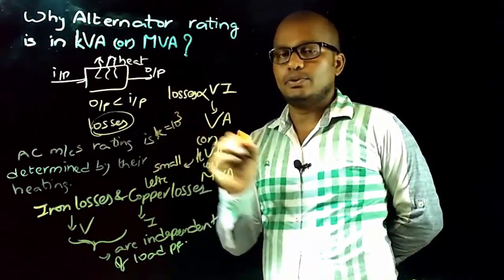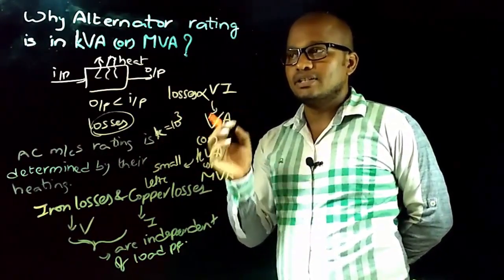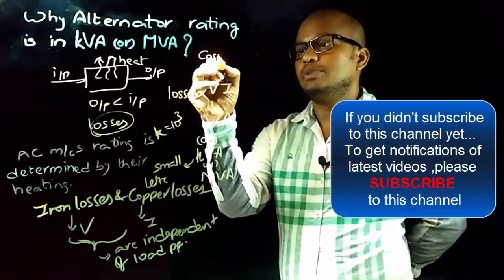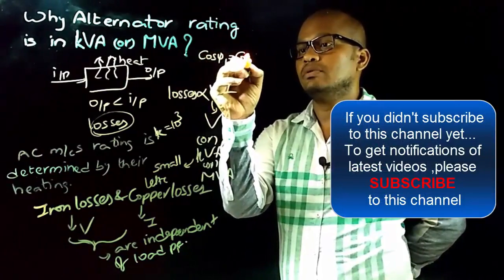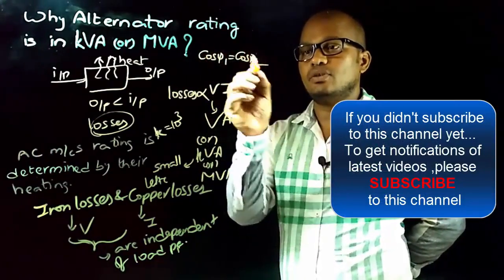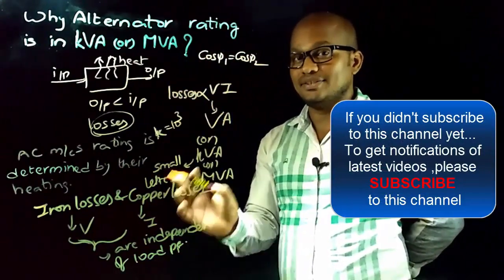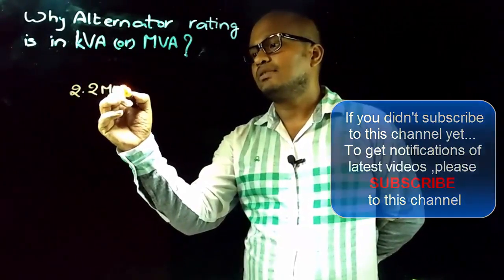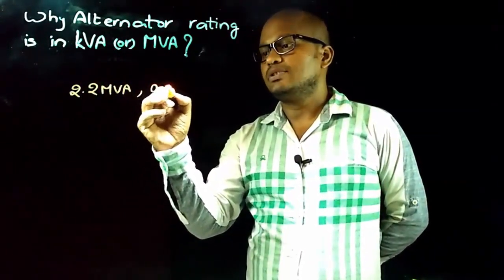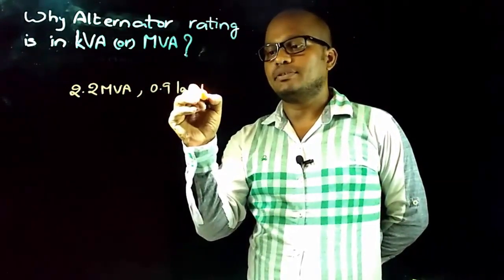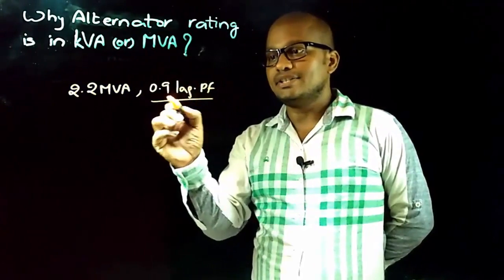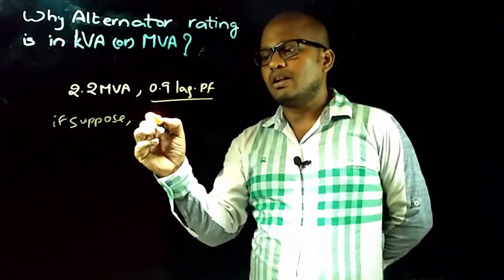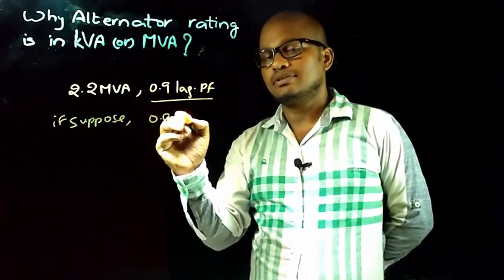From the transformer topic, transformer losses are independent of power factor because input power factor equals output power factor. But the alternator case is different. On the nameplate details of an alternator, it will be specified as, for example, 2.2 MVA at 0.9 power factor, which means that particular alternator is designed to operate at 0.9 power factor at rated load.